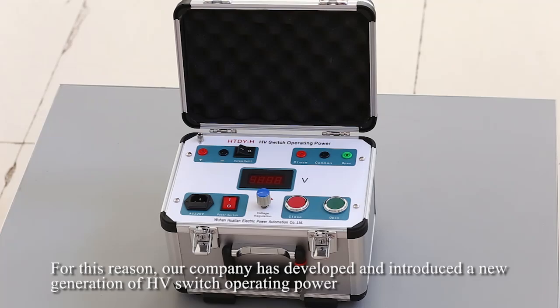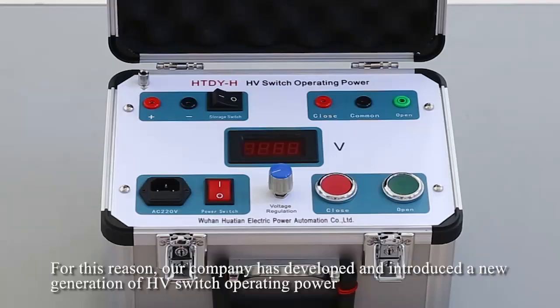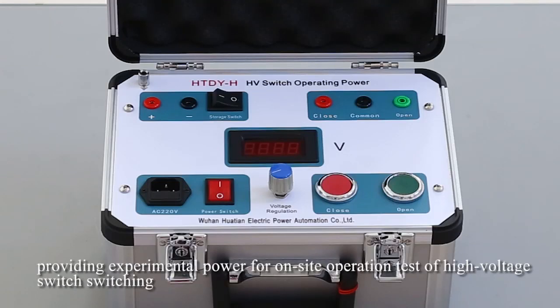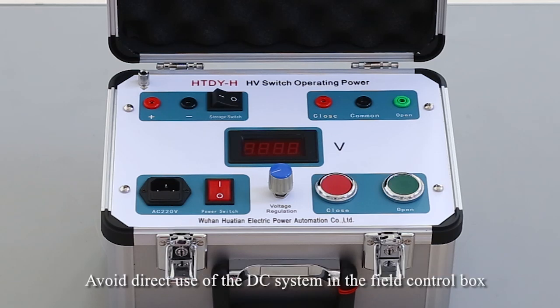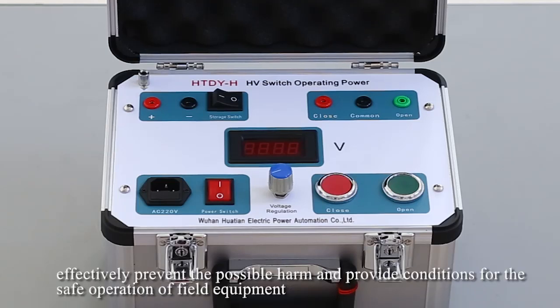For this reason, our company has developed and introduced a new generation of high voltage switch operating power, providing experimental power for on-site operation tests of high voltage switch switching. It avoids direct use of the DC system in the control boards, effectively prevents possible harm, and provides conditions for the safe operation of field equipment.